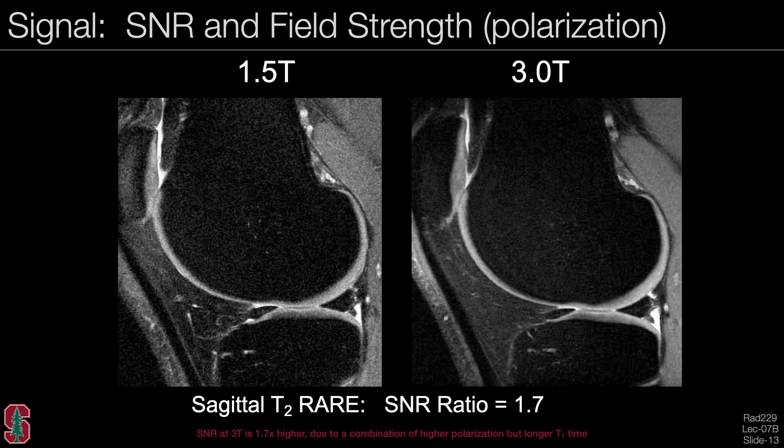Looking at field strength: as shown in the last lecture, SNR is proportional to the Larmor frequency. Here are two images acquired at 1.5 T and 3 T. The SNR at 3 T is almost twice that at 1.5 T, though not quite, because there is a longer T1 time at 3 T which causes some saturation effects in the sequences. Higher field strength generally means higher polarization and higher signal.